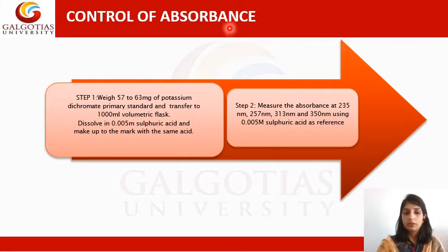Then comes the control of absorbance. In control of absorbance, we check whether the absorbance that you are getting for a particular solution is correct or not. For this also we require a standard. The standard that we use is potassium dichromate. Whenever you perform the calibration of the absorbance scale, the standard that you will use is potassium dichromate.